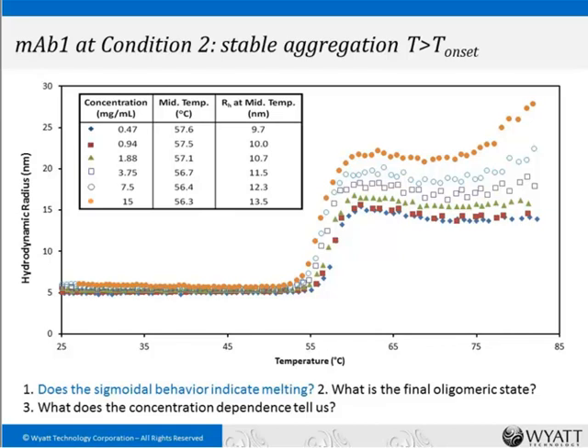The same monoclonal antibody under a different condition shows an aggregation point, but quite different behavior — it settles at a much smaller size, around 15 to 20 nanometers instead of hundreds. There is still concentration dependence. Dynamic light scattering gives more information beyond just the fact of a thermal transition: you can zoom in on the final temperatures and determine the distribution of aggregate sizes, and in principle use DLS to understand the average oligomeric state and size of aggregates.